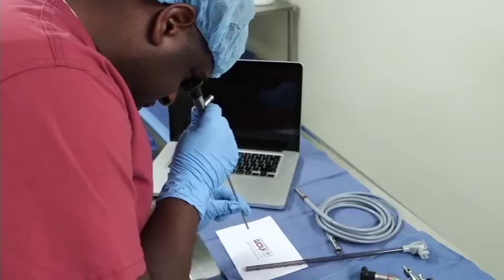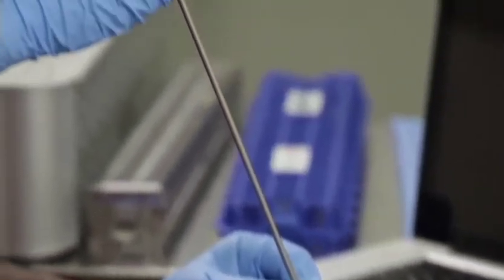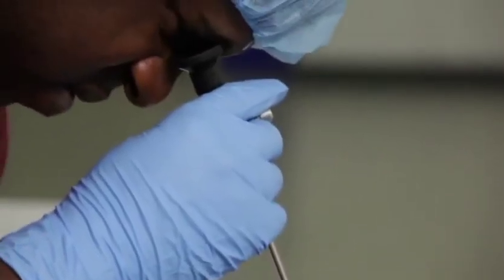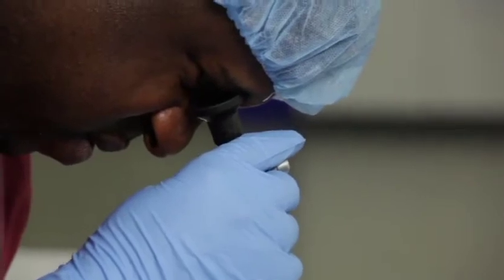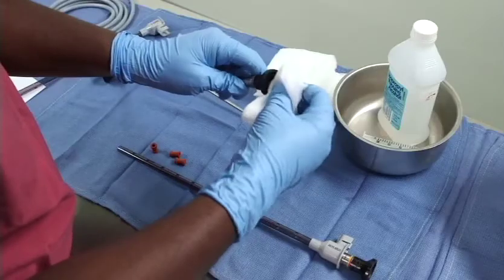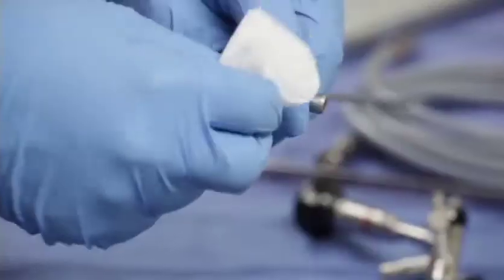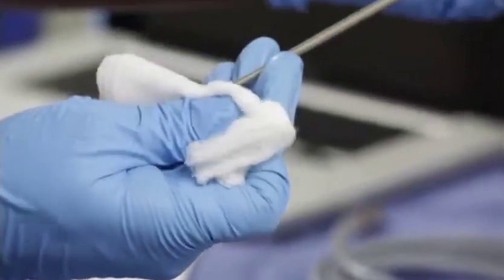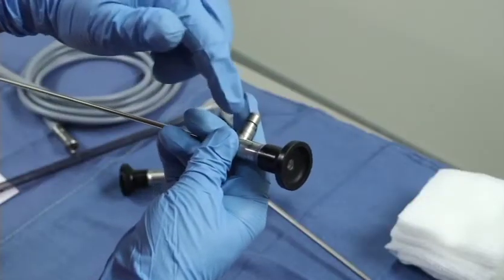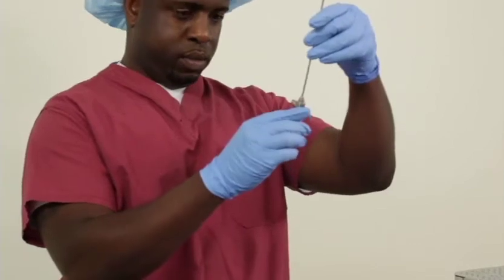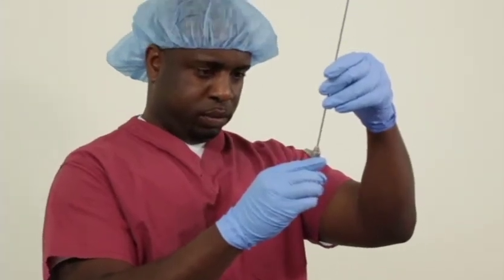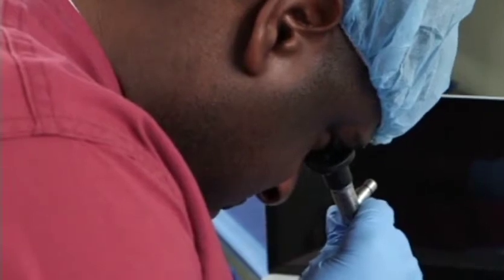Look into the eyepiece and focus on a surface 3 to 5 inches away. The image should be clean and crisp, with no fogging or any part of the image missing from view. The objective lens and eyepiece can be wiped with alcohol to remove any cleaning solution residue. Inspect the scope's light quality. Hold the distal end of the scope straight up to the ceiling light and look directly at the light cable post. The post should appear milky white with no black spots.